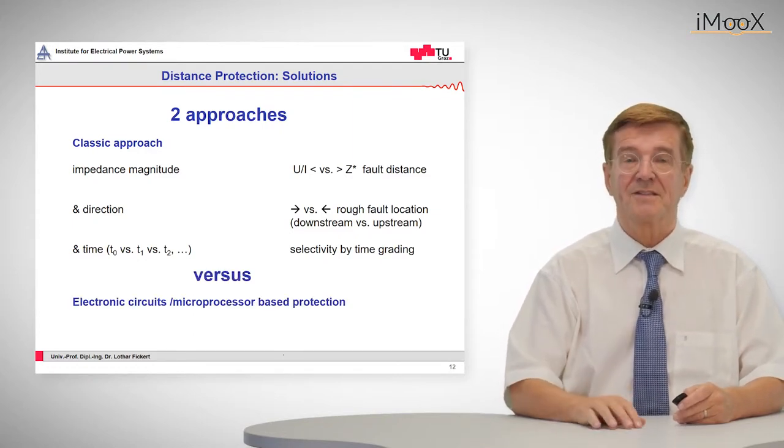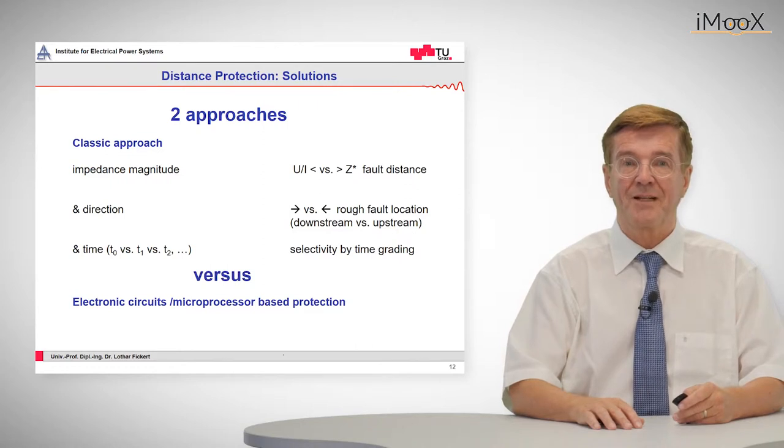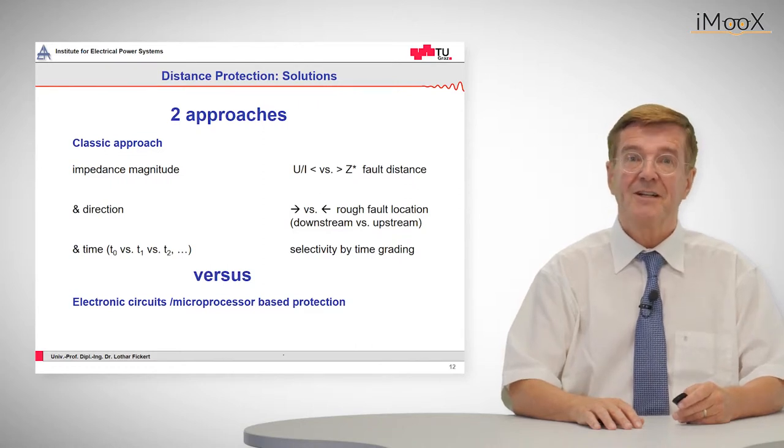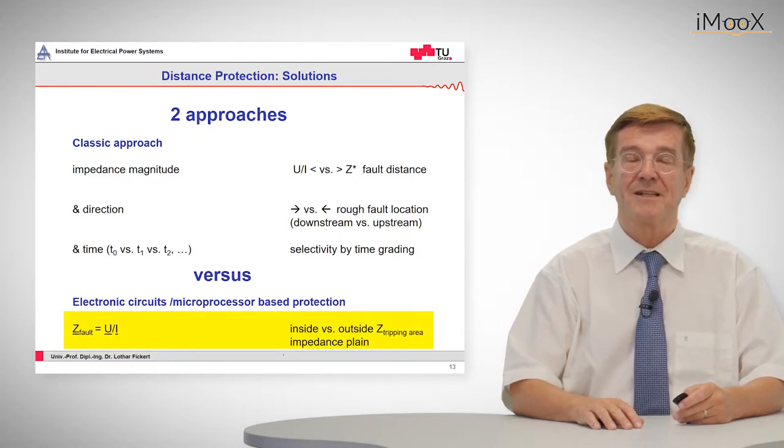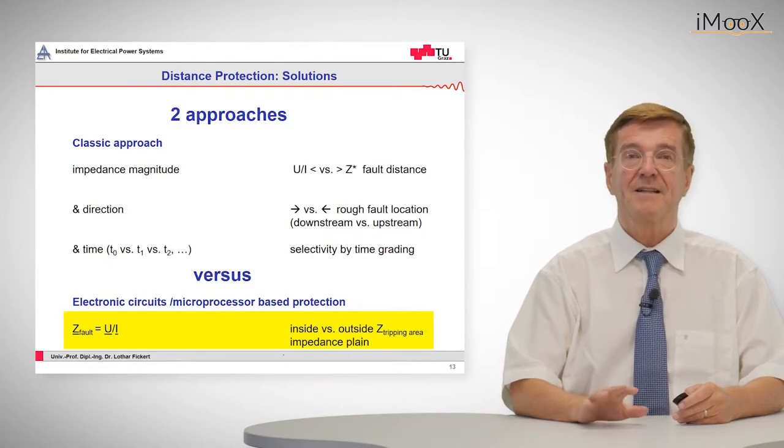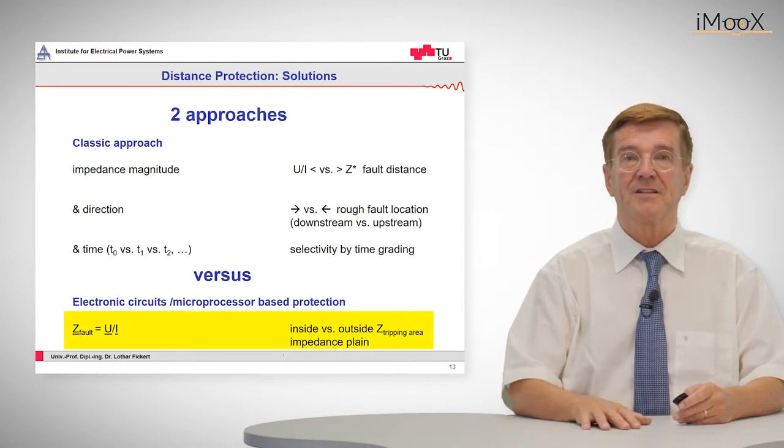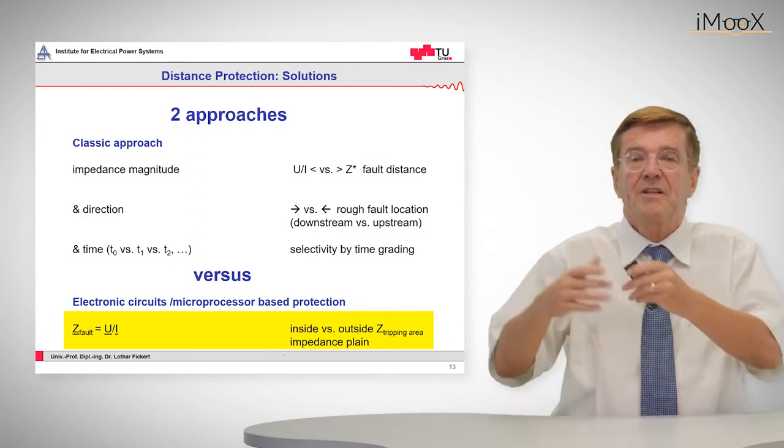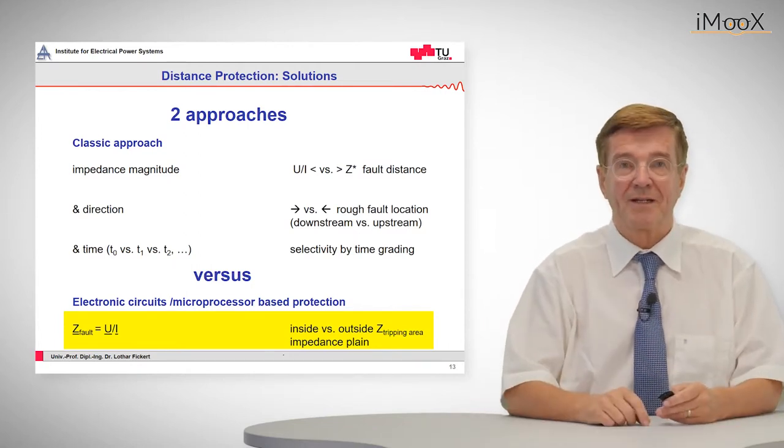And this is versus the electronic circuits or microprocessor protection which just determines in the impedance plane the complex impedance and decides whether it is inside or outside the so-called tripping area.